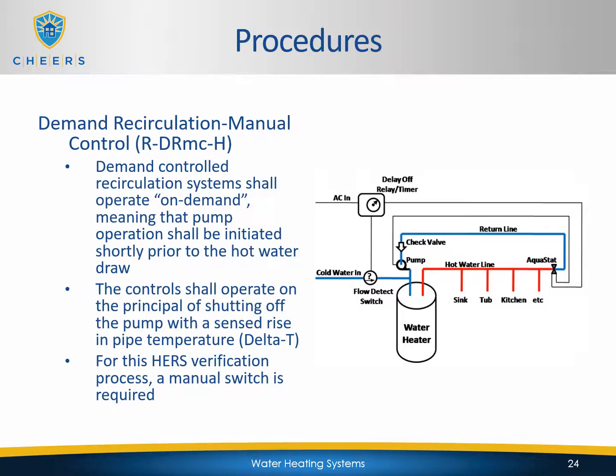Demand-controlled recirculation systems shall operate on demand, meaning that pump operation shall be initiated shortly prior to the hot water draw. The control shall operate on the principle of shutting off the pump with a sensed rise in pipe temperature, or delta T. For this HERS verification process, a manual switch is required. So essentially the way this works is you're going to have 3 pieces to the system. You're going to have a pump, you're going to have a thermal control, and you're going to have a manual button or switch.